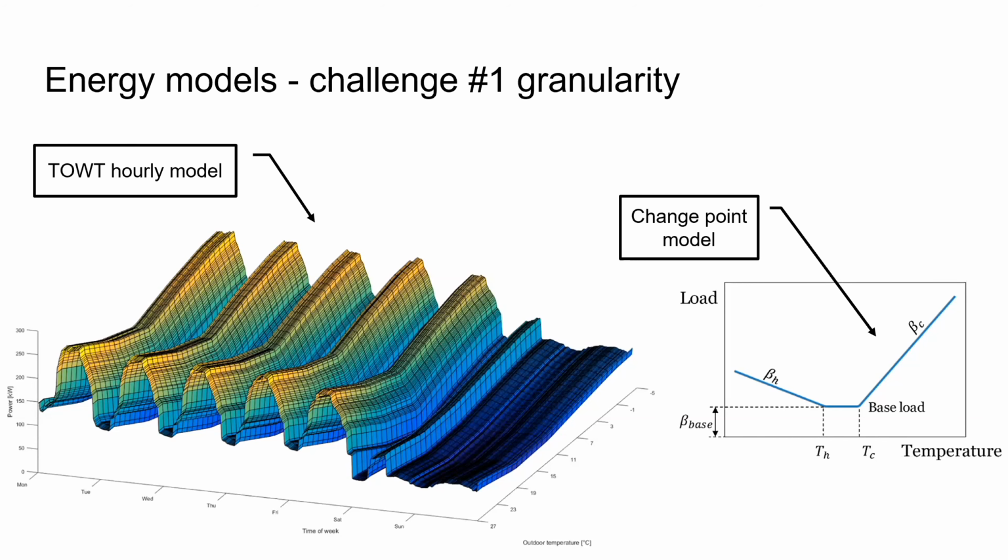Next question is, I assume models are not transferable between buildings or sites due to large variability in the variables. Do you train models for a single site using historical data of that specific site? Yes, this is exactly like that, and this is important to be able to do it like this. It's not the intention to identify a model on one building and try to use it on the other. You should identify a model for each building individually.